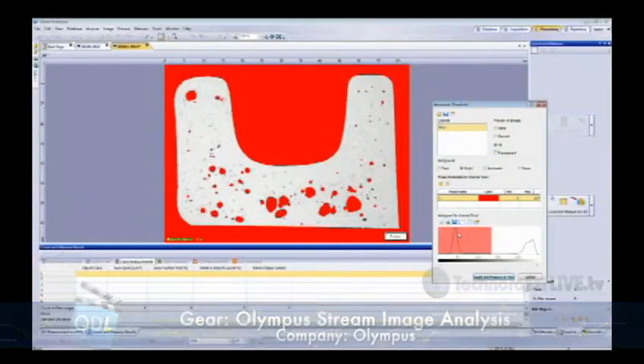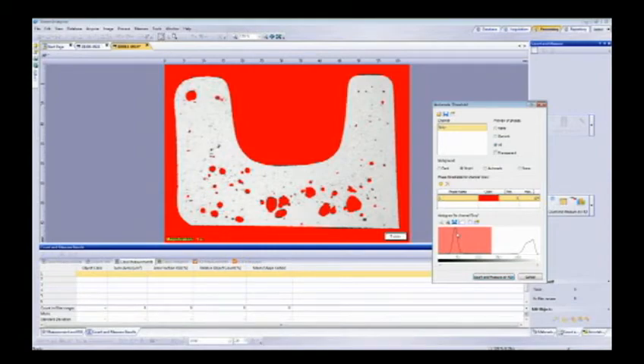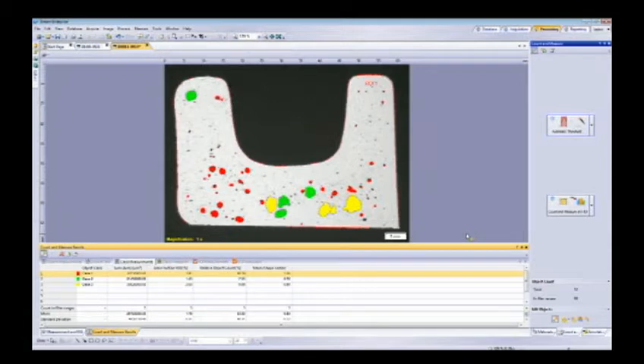The software has the ability to identify and outline a region of interest around this U-shaped metal piece. It allows us through the Count and Measure tool window to quickly do automatic thresholding. Thresholding looks at the intensity of a background compared to whatever you're interested in — it could be by color, by grayscale, or by shape factors. This is the automatic mode, where the software determined the threshold based upon the histogram and automatically set the levels. Later on, I'll show a live one as well.